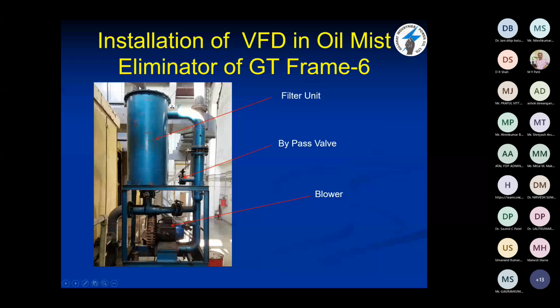You can see that this is the oil mist eliminator. This is sucking vapor from the gas turbine. This is the whole system. This is the pump, a vacuum pump that is operating for creating vacuum in the system. And this is the filter. It will suck all the fumes from this tank, and the remaining oil will go back to the tank, and fumes will go out. So it was already designed for base load operation, and as per part load operation, we have fitted a VFD. Now this motor is running at different RPM, and that is a huge saving in power consumption.